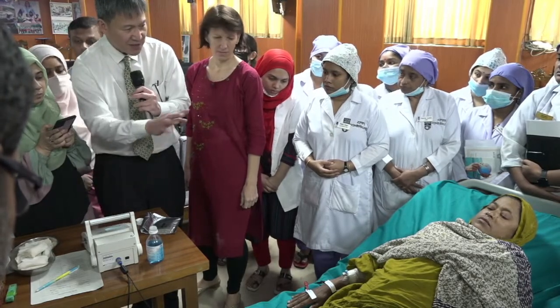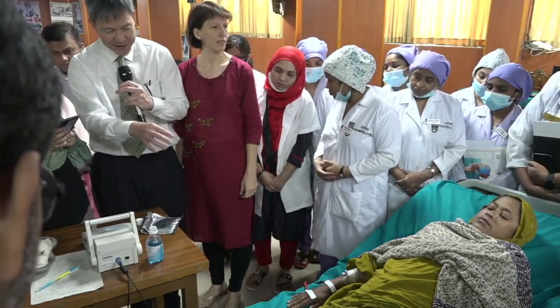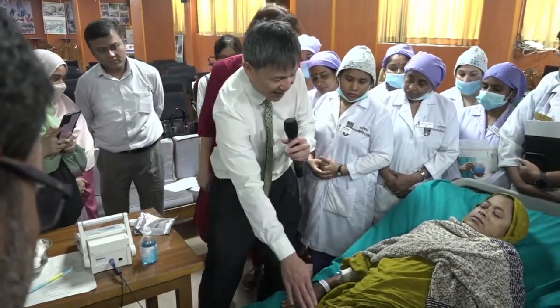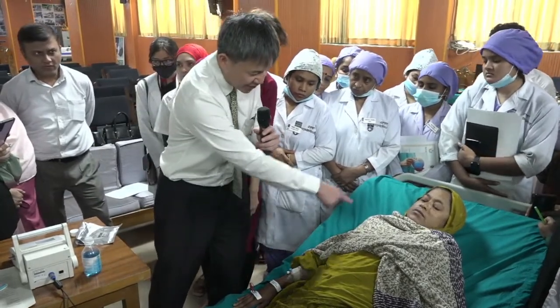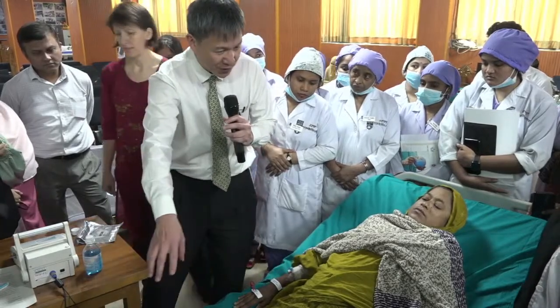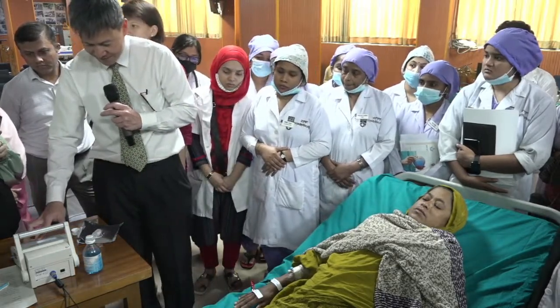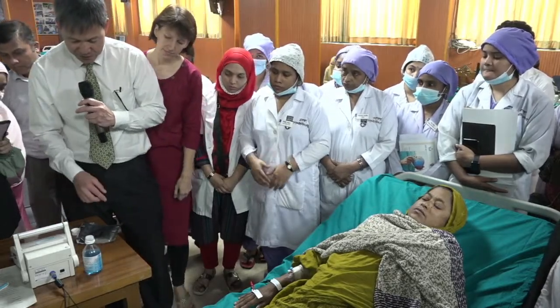Okay, so if you just tell her, whilst this is measuring, I know she's lying very flat, so just stay lying flat. And it's important that she's not touching herself, because otherwise she's short-circuiting. So if her hands were lying on her legs, for example, then she may be short-circuiting. You want the electrical current to go through the whole body. So that's excellent. If she was crossing her legs, that would cause complications. So the way she's doing is perfect, and she's not moving around, perfect. So one beep to start measuring.